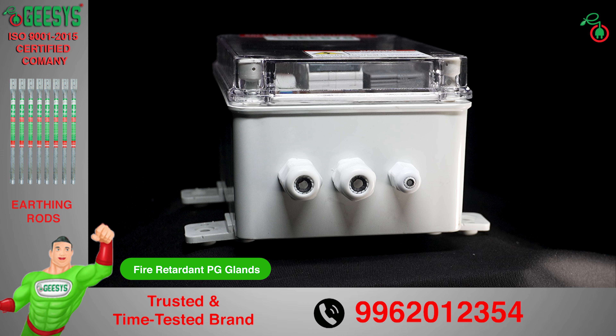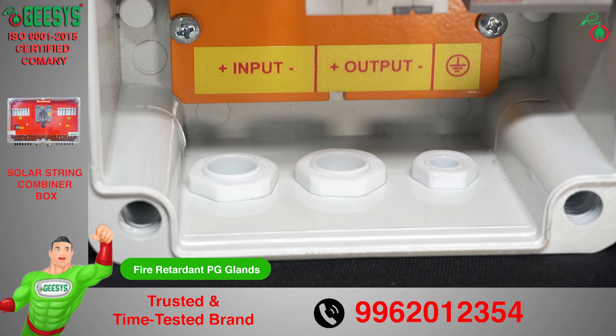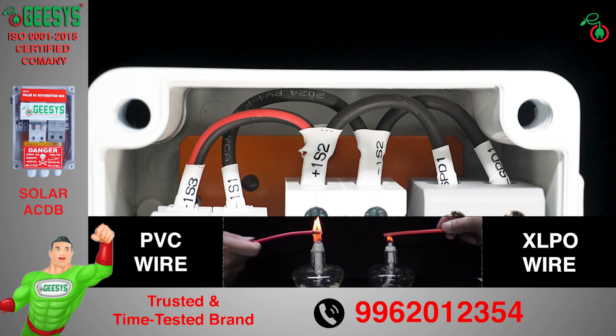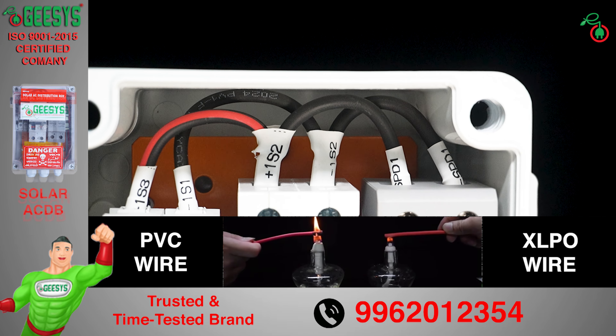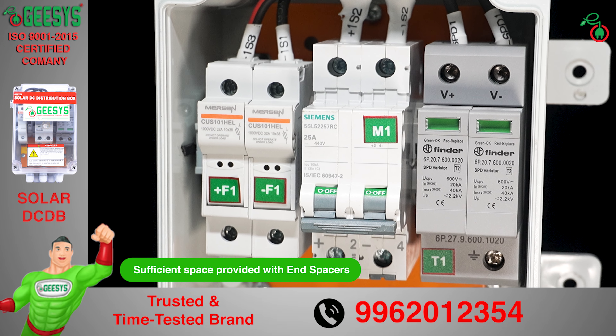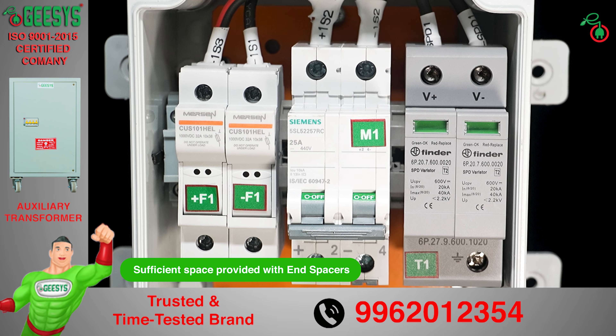The input, output, and earth cable entries are from the bottom through fire-retardant PG glands. GEESYS uses only XLPO-insulated solar DC cables, which are fire-retardant and UV-protected. Sufficient space is provided with end spacers between components, especially between the MCB and SPD, to reduce the intensity of fire in case of abnormality.